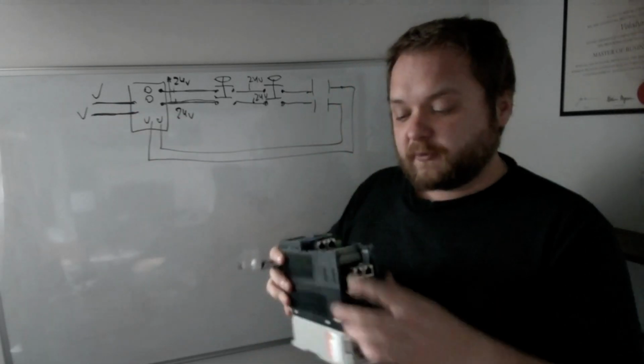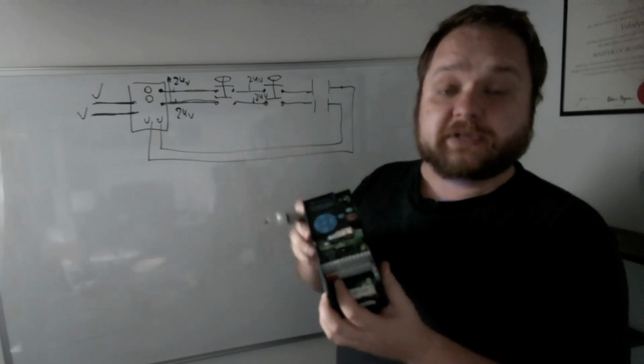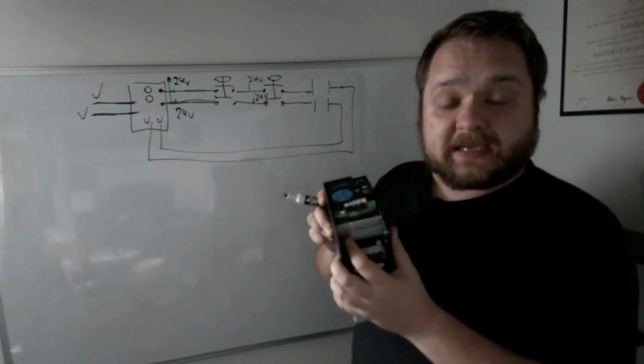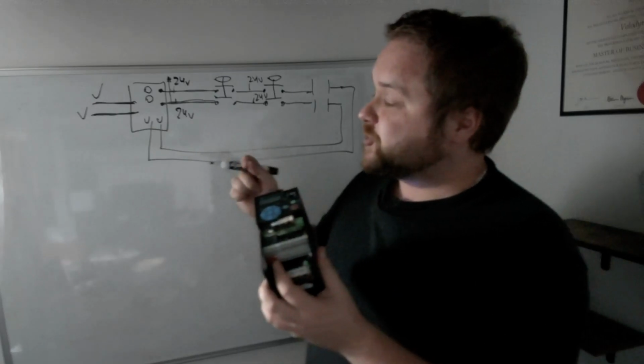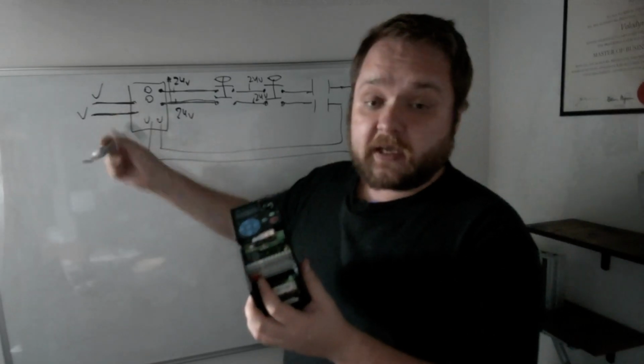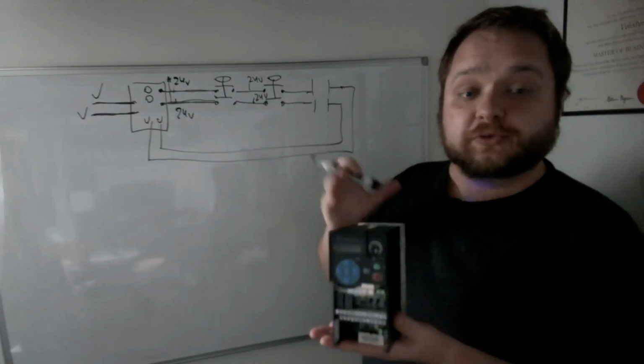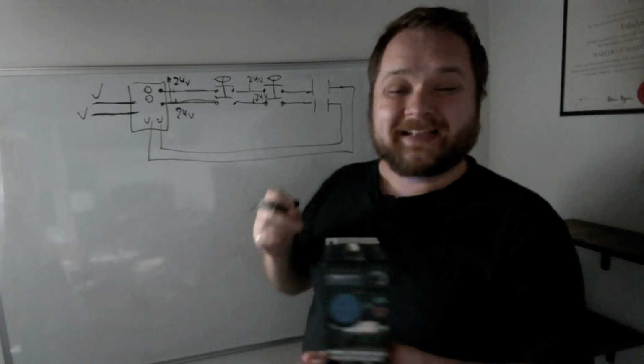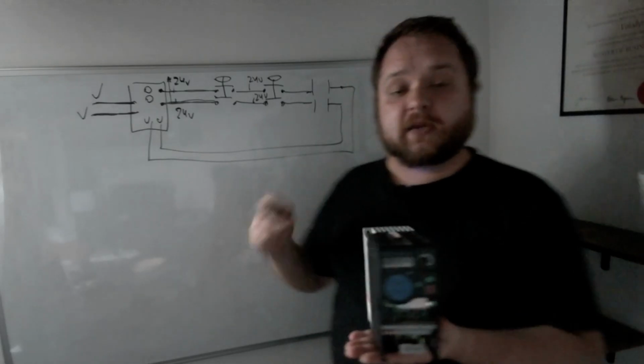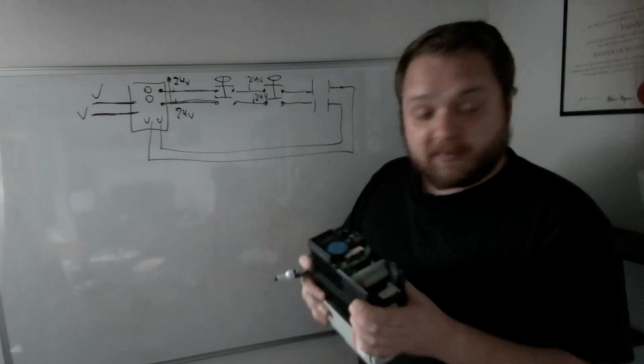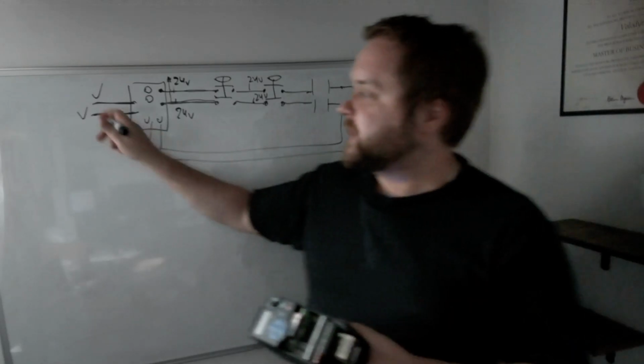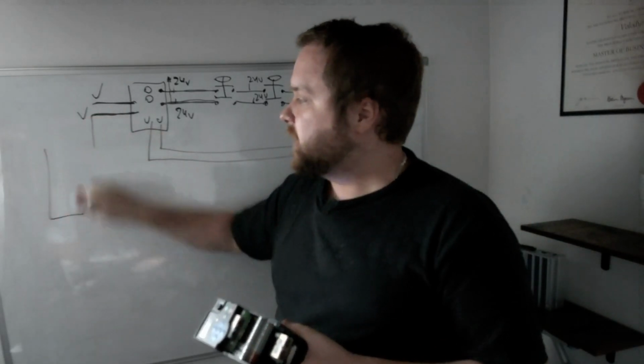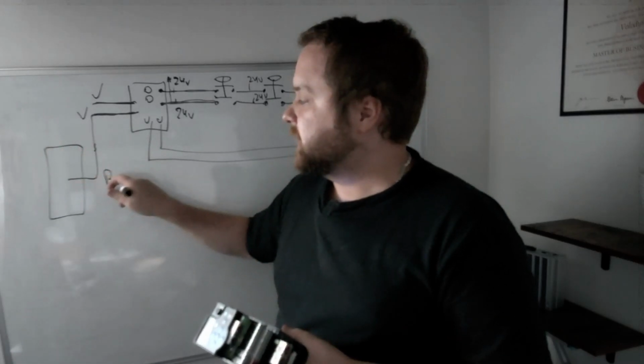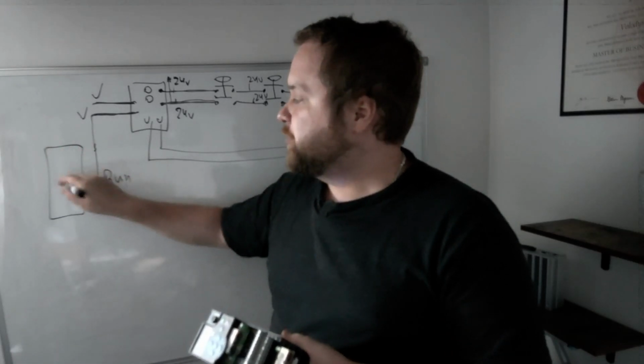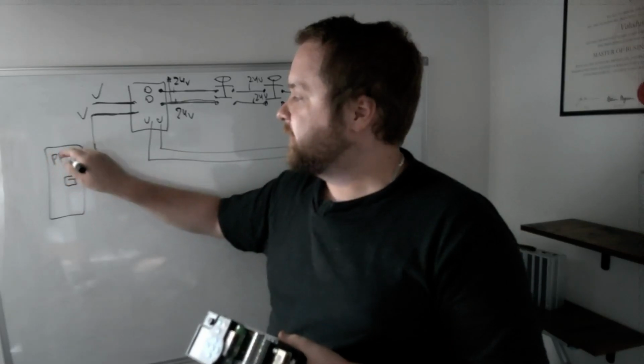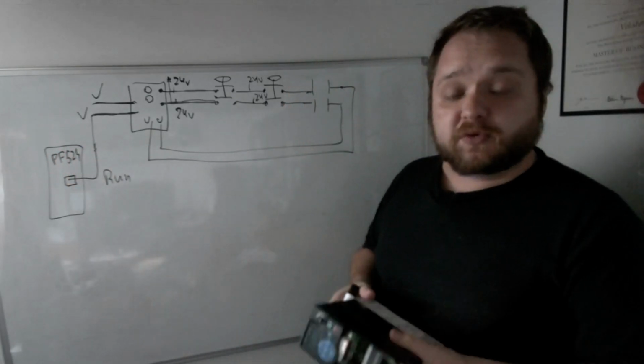And only if both of those channels are okay, again, you can program some internal confirmations. This is going to be coming in with a jumper, but only if those channels are okay, and if it's enabled, is this PowerFlex going to be allowed to run? So it is very important that you wire this correctly if this is a requirement for your specific application, because basically it is not enough to, for example, take one of these channels and wire this into a PowerFlex on the run side. So if you do something like this, where you plug in the PowerFlex, in this case it's a 525, but it's standard across most VFDs nowadays.